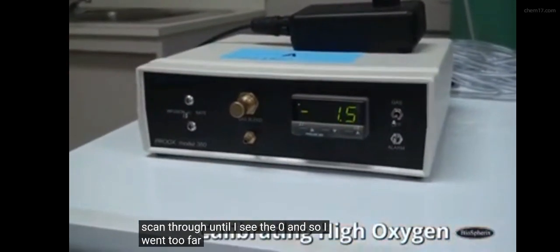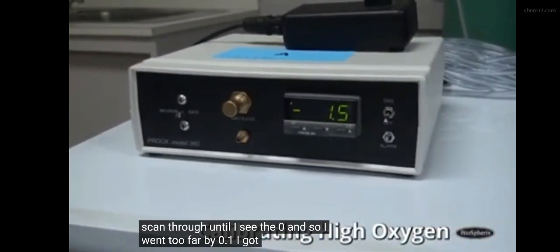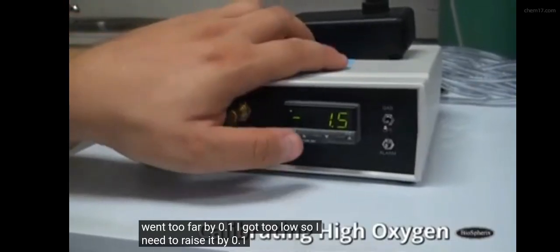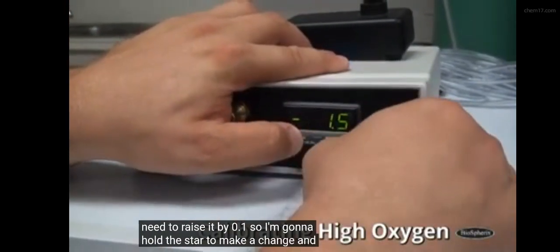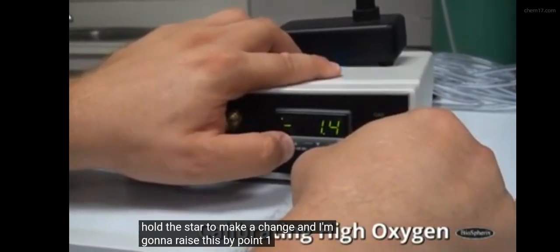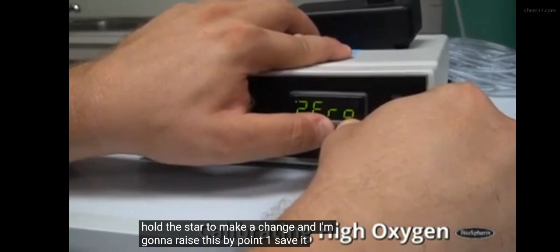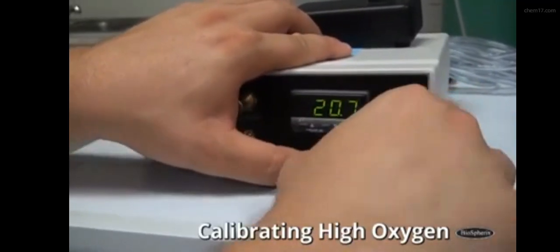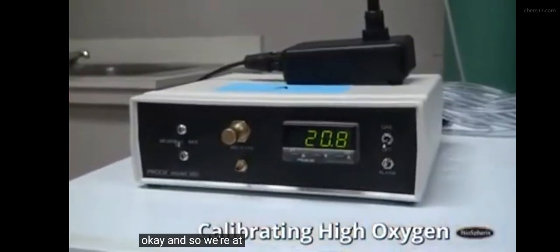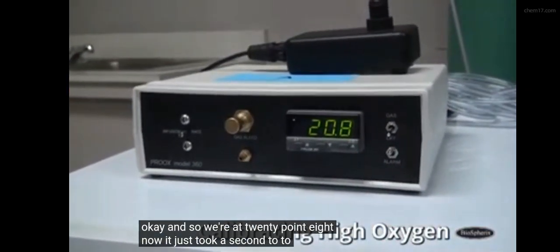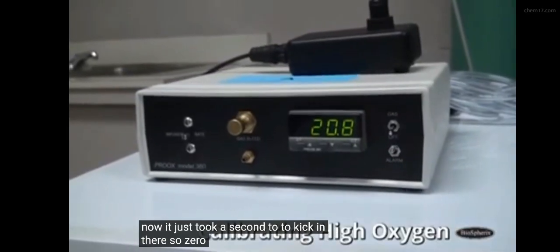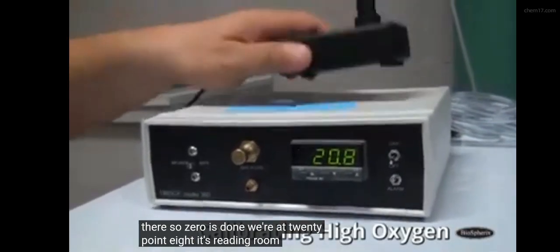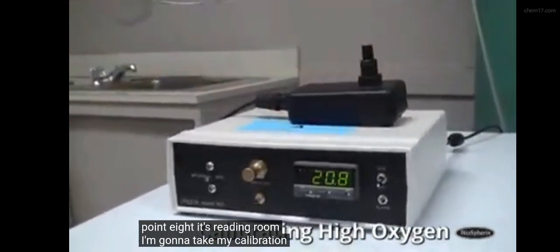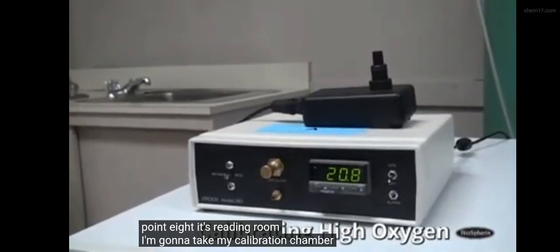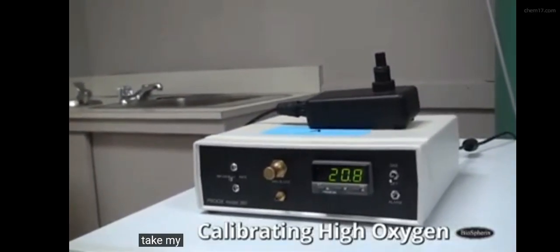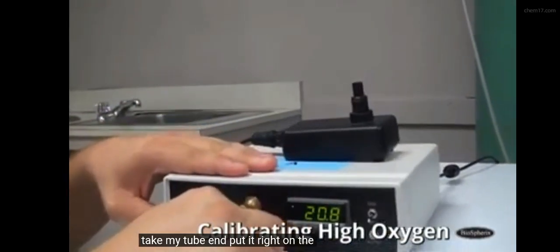And so I went too far by 0.1. I got too low, so I need to raise it by 0.1. So I'm going to hold the star to make a change, and I'm going to raise this by 0.1. Save it. Okay, and so we're at 20.8 now. It just took a second to kick in there. So 0's done. We're at 20.8. It's reading room air.